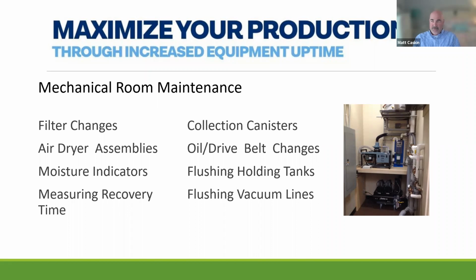And then another thing I wanted to mention was going back to the space requirements. You want to make sure that your mechanical room is big enough and climate controlled for your equipment. So heat and humidity are your main enemies for your mechanical room. So you want to make sure when you're setting these up, and again, these are in the manufacturer guidelines, you're providing cool, dry air to the room. You don't want to put these things outside. We've seen instances where they're outside in a shed, and being from Florida where I work, that's just not a good thing. You want to make sure when you're designing your office or you're upgrading your office, you're providing a good, clean space with fresh air to put your utilities in, and try not to clutter up that area. So we'll go to the next slide.